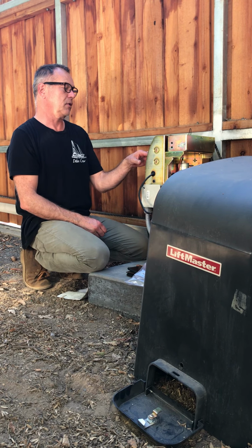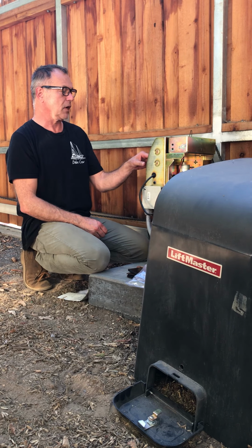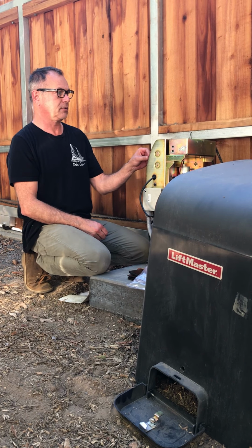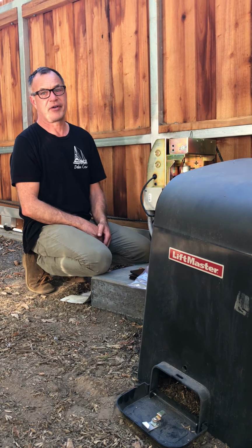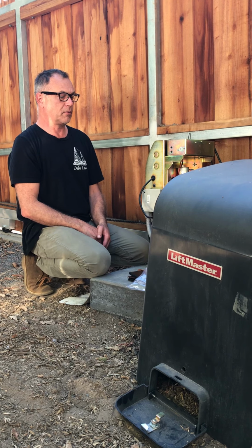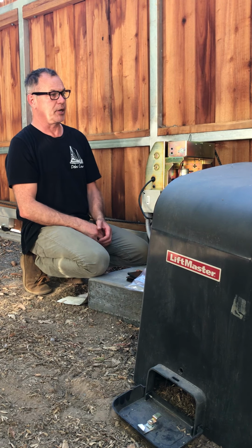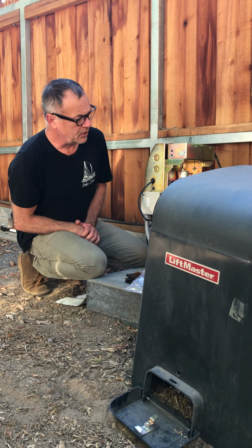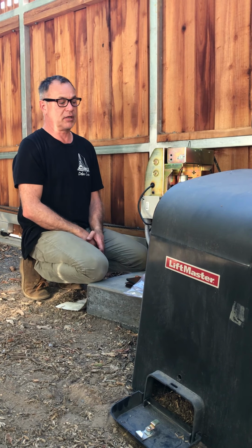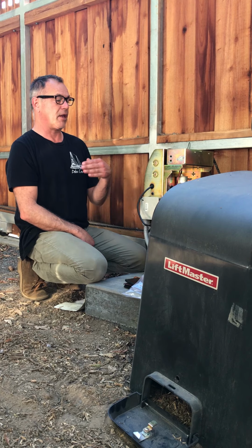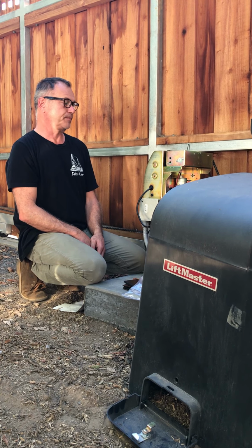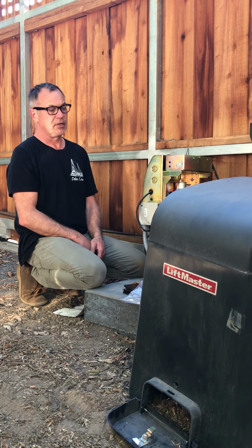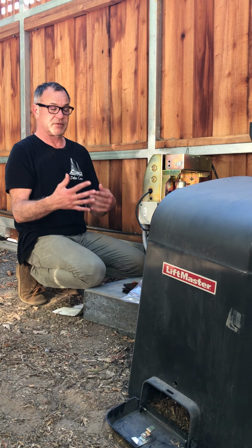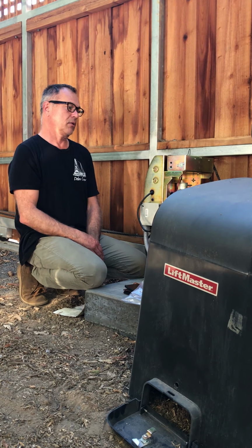So we can get it to work a little bit, it'll run a little bit and stop and give me an error code 9.5. So that means the motor is overdrawing current, but in its current configuration, we've taken off the belt and completely unloaded the motor and then advanced it by hitting the test open and close buttons, spinning the motor, and it still gives us that error code 9.5. So where's the error code, does it show it? Yeah, the error code is right here.